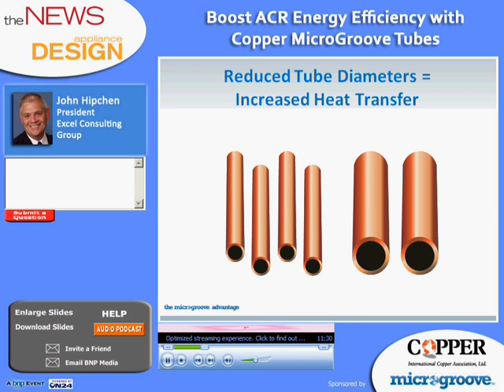When we compare tubes of different diameters, the first thing we might notice is that it will take several smaller diameter tubes to equal the surface area of a larger diameter tube. This is not a disadvantage. We actually have some important benefits here. A big one being an increase in the surface area to volume ratio, and that equates to more heat transfer. And with this increase in heat transfer, we don't need to match the volume or surface area of the larger tube to get the same amount of cooling.